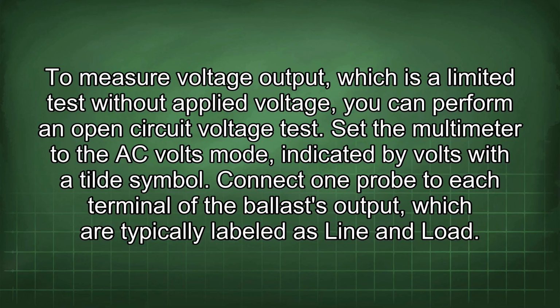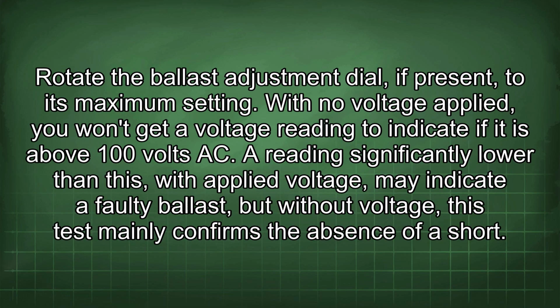open circuit voltage test. Set the multimeter to the AC volts mode, indicated by volts with a tilde symbol. Connect one probe to each terminal of the ballast output, which are typically labeled as line and load. Rotate the ballast adjustment dial, if present, to its maximum setting. With no voltage applied, you won't get a voltage reading to indicate if it is above 100 volts AC. A reading significantly lower than this, with applied voltage, may indicate a faulty ballast, but without voltage, this test mainly confirms the absence of a short.